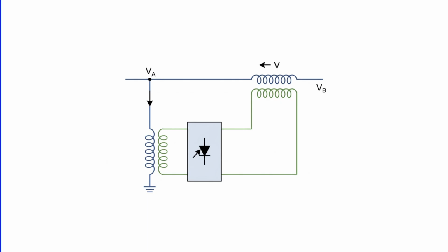Because it controls power flow by controlling the phase angle difference across the line. Remember our power equation: power transferred depends on the sine of the angle delta. If we can control delta, we can control the power flow. And that's exactly what phase shifting transformers do.